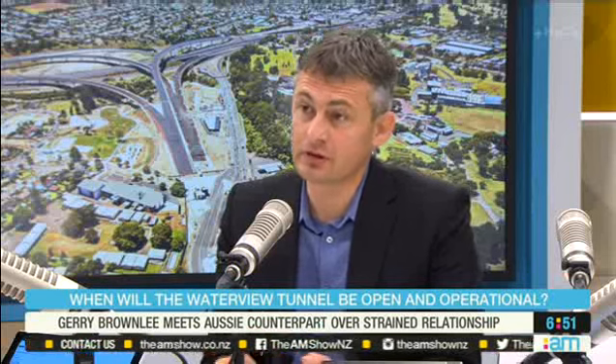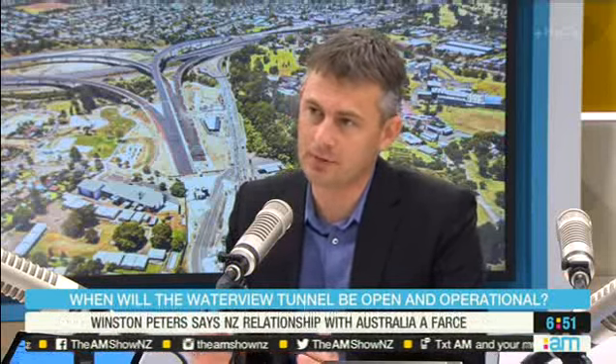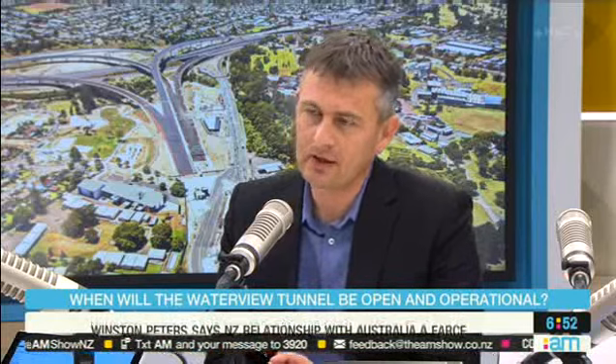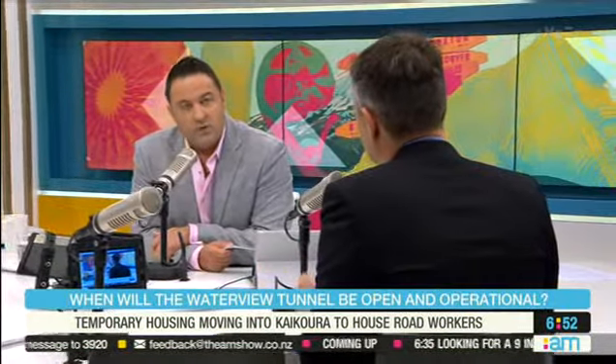Good morning. What happened? Yeah, so a lot of the rumours are incorrect, I can assure you of that. What happened is we're testing a whole lot of equipment to go into this tunnel — fire life equipment, really critical equipment — and some of it just wasn't operating as we wanted to. We had some issues with some valves that opened the deluge system and some issues with the jet fans. We're now over those, so we've got those systems working, and we're now in the phase of testing the tunnel as a whole complete system, testing all the equipment together.